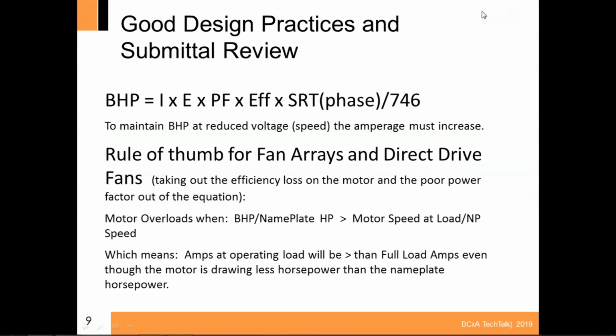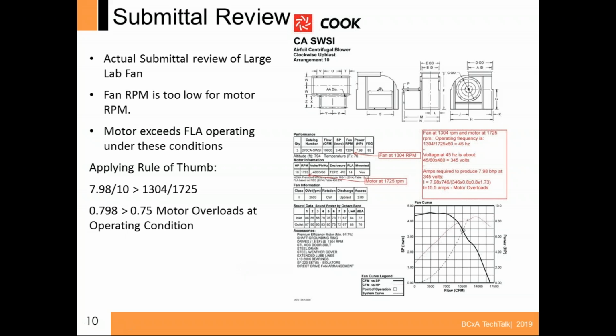Let me go ahead and see if I have anything going on. Okay. This slide is an actual submittal review that I did. In this case, it was a Cook centrifugal blower for a laboratory. It's a pretty good size fellow, too. It's a 10,600 CFM blower running at about 3.4 inches of external. They submitted it as a belt drive, and the engineer came back and said, no, we want to have a direct drive. So the vendor just said, okay, direct drive, and left everything exactly the same.